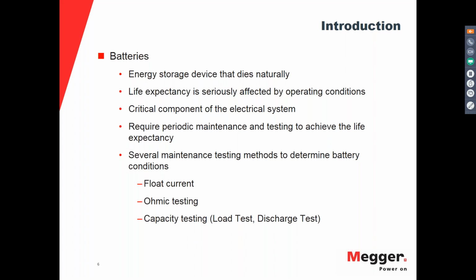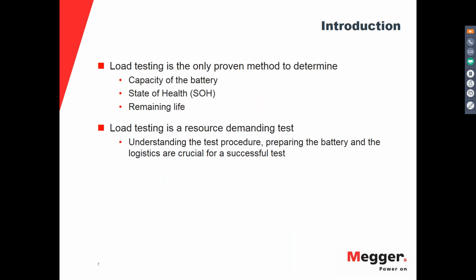And then you have the capacity testing, which is the one that we are talking about today. This capacity testing, also called load testing, is the only proven method to determine the actual value of the capacity of the battery. It's also the only way to determine the state of health of the battery, or to see what is the remaining life in the battery. The other methods are just an indication of what that capacity could be, and there's no direct correlation from those methods to the actual capacity value of the battery. So it's the best test that you can run on a battery.